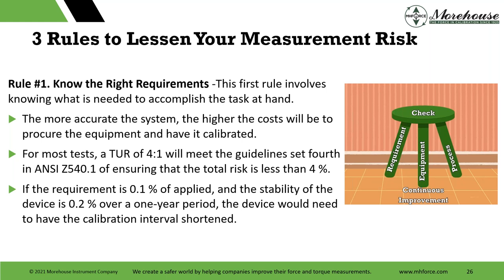If you constantly keep tweaking your calibration intervals, it's very difficult to get reliable specs. Howard Kastrup once quoted that if you consistently did this with a large number of pieces of equipment, it would take you 60 years to figure out the optimal interval. I'm just saying shortening the interval is one of several solutions. Maybe the better solution is just to consider replacement, or buy better equipment with a reliable manufacturer that actually has a good stability spec.